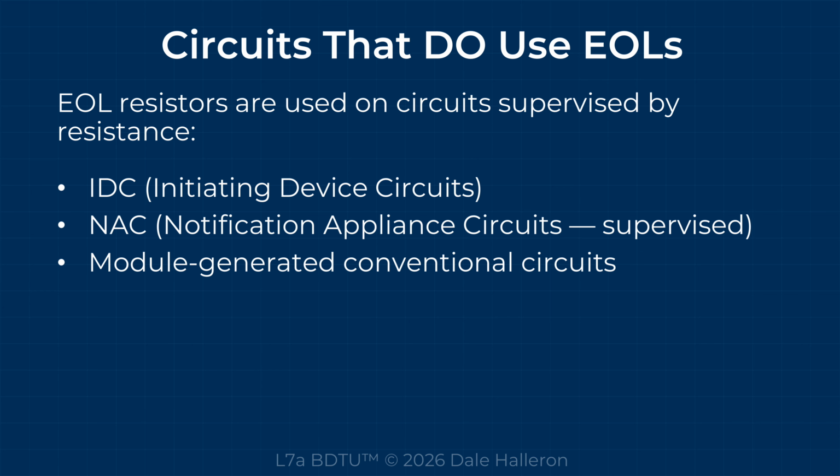Circuits that do use EOLs. EOL resistors are used on circuits supervised by resistance. IDC, initiating device circuits. NAC, notification appliance circuits. Module-generated conventional circuits.